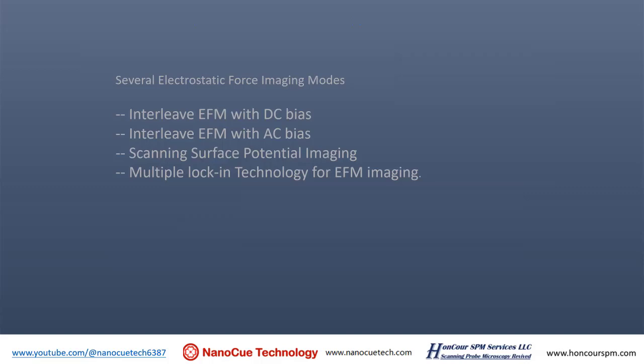That's MFM. For long range force imaging, EFM can also scan and sense the tip's electrical static force, and we call it electrical force microscopy or EFM. There are many different ways to image EFM: interleave EFM with DC bias, EFM with AC bias, and scanning surface potential imaging. The scanning surface potential is no longer called EFM — it's called Kelvin force microscopy. You can also use multiple lock-in technology to do EFM imaging.